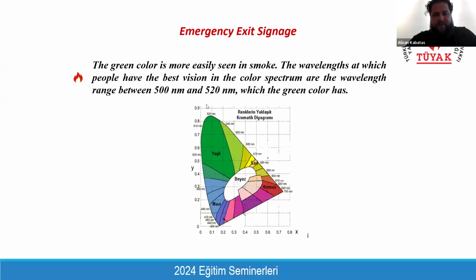When you see the spectrum of this visibility according to the colors within the smoke, the green color is the most easily seen spectrum. It has the larger spectrum. That's why the exit signage are determined to have green background and white pictogram level. That's why we cannot change it. It is written in the Turkish fire code, even if it is not parallel to your interior architectural design.